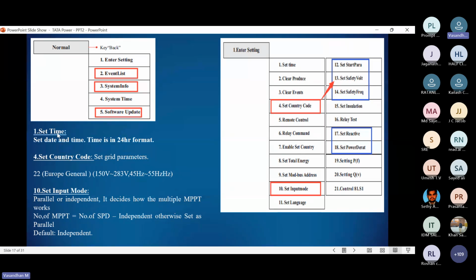The main thing is there are only three settings you must do manually while commissioning the inverter. First, set time — go to the set time option, using 24-hour format. Then go to enter settings and select set country code, such as Europe General or 022 for our Indian standard code, and set the grid parameters.